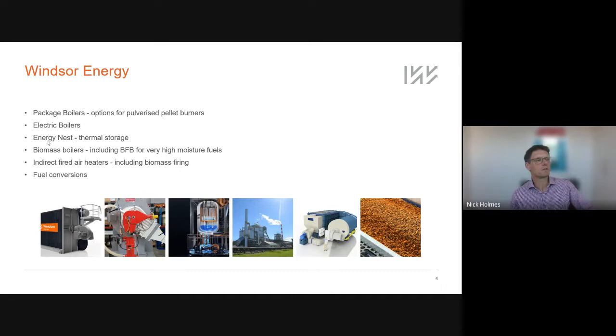In terms of the electrical boilers, we're also looking at thermal storage. We've got a partner in Europe that has Energy Nest thermal storage, using large inertia, with the ability to store heat in that thermal mass. So you can charge them up with low cost electricity during the day, especially here in Australia with almost negative electric charges during the day, store up thermal inertia during the day and discharge at night for the process, whether that's steam or thermal oil through a heat exchanger.